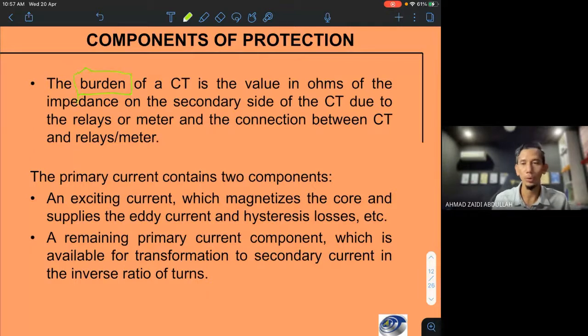Okay. Normally, when we want to buy or check the characteristics of our CT, we refer to the burden. Burden ni apa? Burden ni, its value is in ohm. We check the value. Okay. And then this is the secondary part lah, the secondary side of the CT, due to the relay or meter connection. So just check how many burden the CT has.